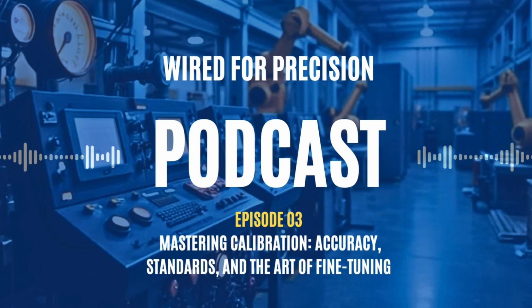5. Environmental conditions. Instruments exposed to harsh environments, vibration, humidity, corrosive gases, should be checked more often. 6. Usage frequency. A flow meter in continuous 24/7 operation will wear faster than one used once a week. Many organizations adopt a risk-based calibration strategy using a combination of failure mode analysis, process impact assessment, and real-world drift trends. Some also use automated calibration management systems to analyze trends and adjust intervals dynamically.